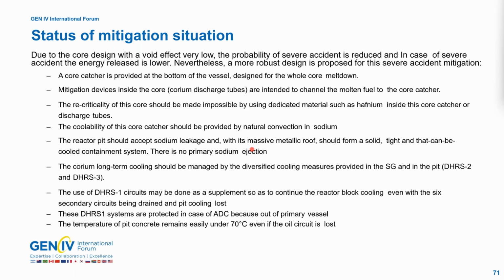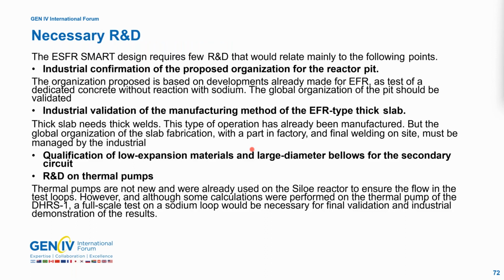can be used as a supplement to continue the reactor block cooling, even if we lose all the other systems. These systems are protected in case of a severe accident, because they are out of the primary vessel, and the temperature of the pit concrete remains easily under 70 degrees in all cases, and even if all the circuits are lost. So we have a very good status for mitigation situations. What research and development do we need to demonstrate all these improvements? It's relatively low.